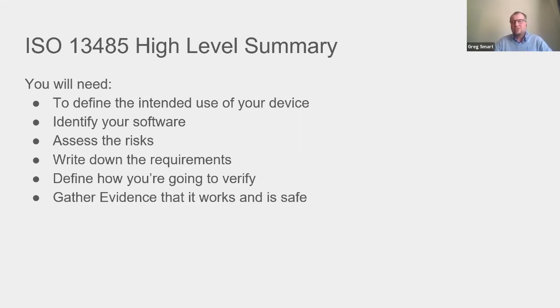Now, in software, that doesn't really translate. We don't tend to track the actual installation of a piece of software. You might, I suppose, for example, with an app, you might track the IMEI and the user registration account. But it's not really quite the same. So my advice really here is that the release note is your friend. When you release your software, if you produce a release note, that can be the thing that identifies that release, and that is the code that goes with it. However you decide to do your release numbering, that's your device identifier.